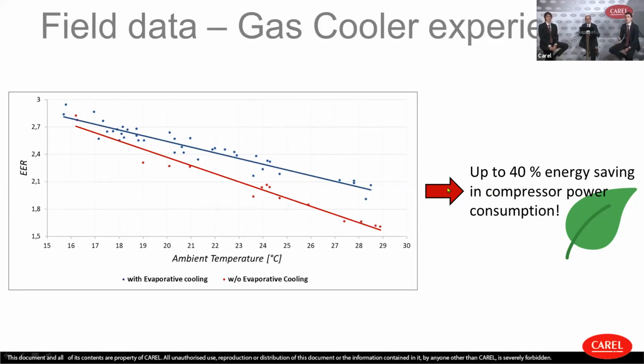You see how, as the temperature grows, the difference between these two systems grows too. It is incredible: when we reach, let's say, 28 degrees, we got an EER index of efficiency of around 2 with the system, and 1.6 or so without it. So it's a terrific gain in efficiency at high temperature. As written here, with the system we got more than 40% energy saving in compressor power consumption. That's the thing, we experienced it, and I think it was interesting.